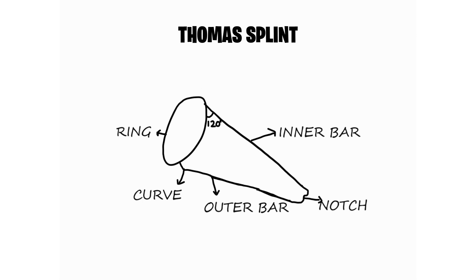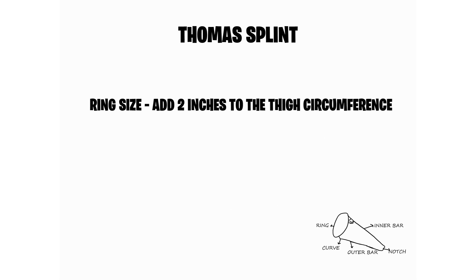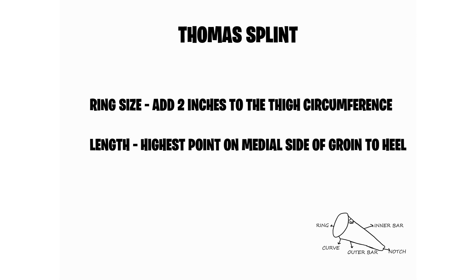Now let's see about the Thomas splint. In this picture, you can see the parts of the Thomas splint: we have a ring, an outer bar, and an inner bar. The outer bar has a curve in its upper part to accommodate the greater trochanter of the femur, as that part of the lower limb is a bit wide. The ring size of the Thomas splint is calculated by adding two inches to the thigh circumference of the patient. The length is calculated by measuring from the highest point on the medial side of the groin to the heel, then adding six inches.